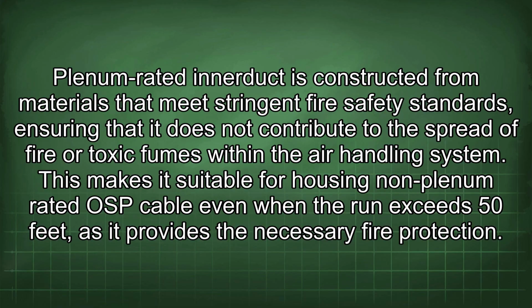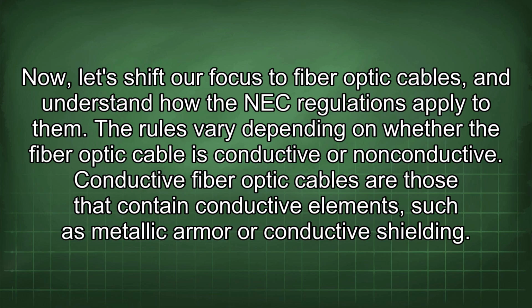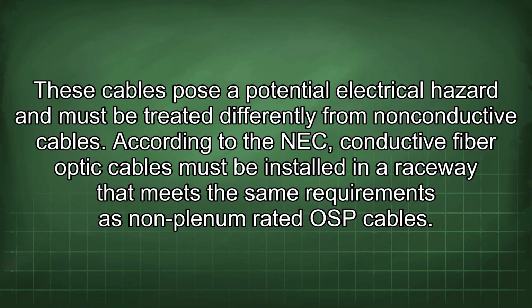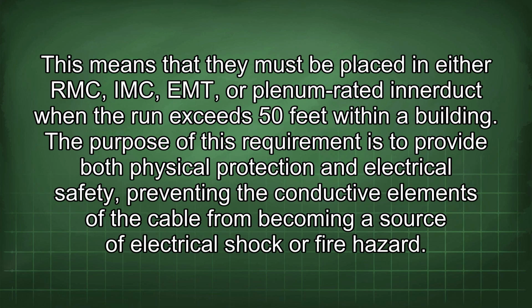Now, let's shift our focus to fiber optic cables and understand how the NEC regulations apply to them. The rules vary depending on whether the fiber optic cable is conductive or non-conductive. Conductive fiber optic cables are those that contain conductive elements such as metallic armor or conductive shielding. These cables pose a potential electrical hazard and must be treated differently from non-conductive cables. According to the NEC, conductive fiber optic cables must be installed in a raceway that meets the same requirements as non-plenum rated OSP cables. This means that they must be placed in either RMC, IMC, EMT, or plenum rated innerduct when the run exceeds 50 feet within a building.